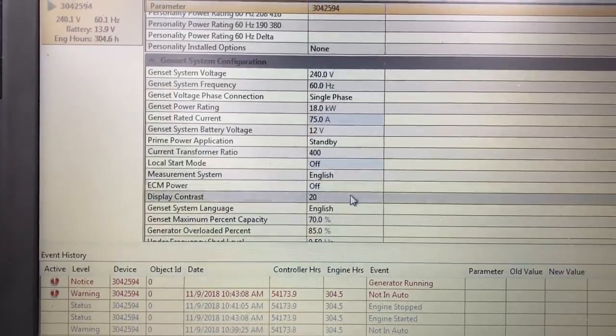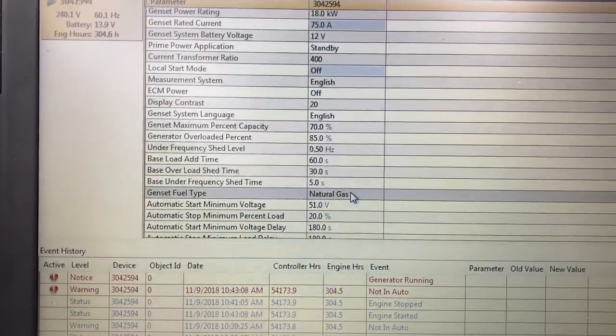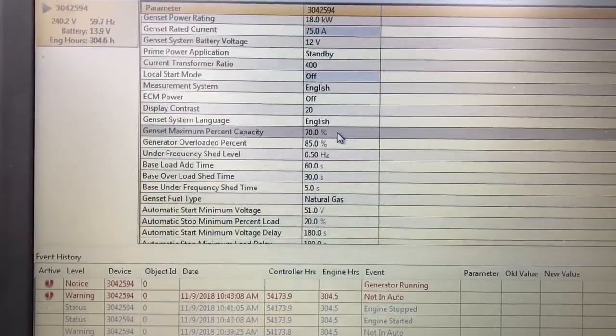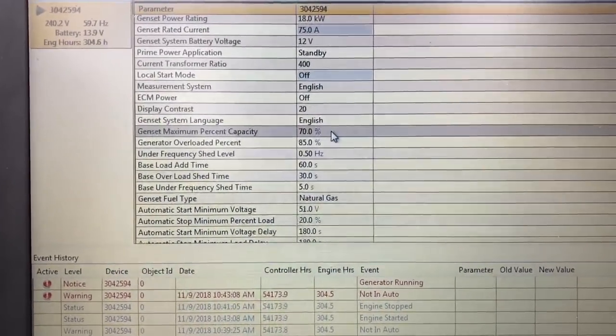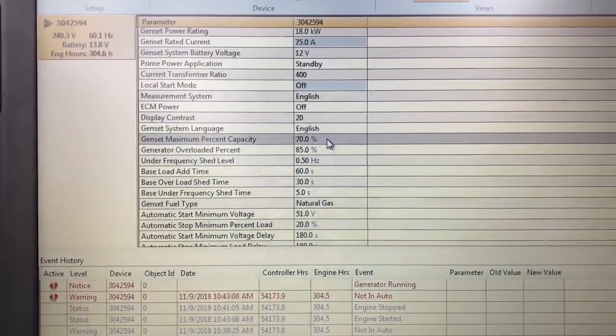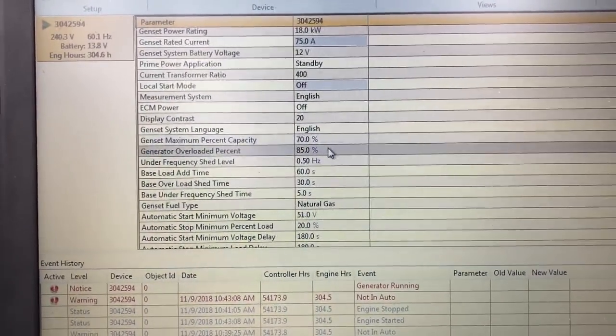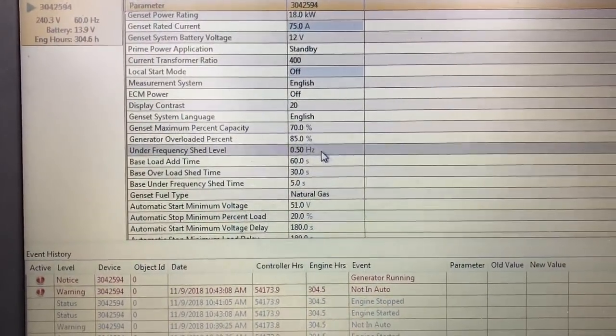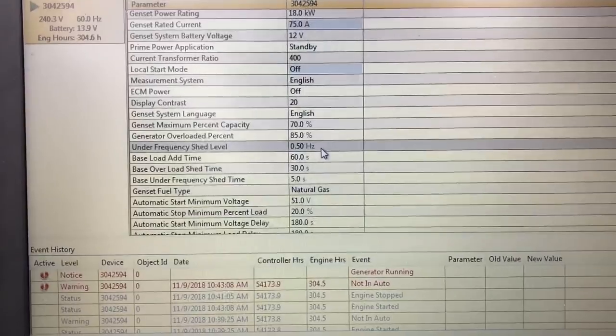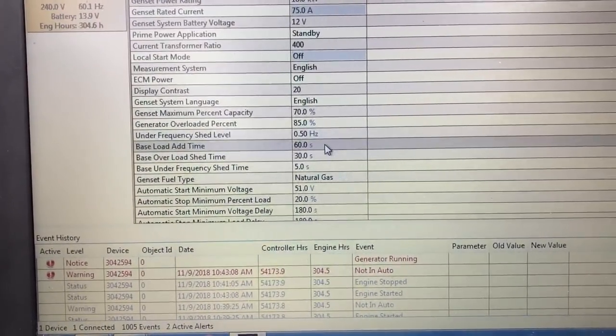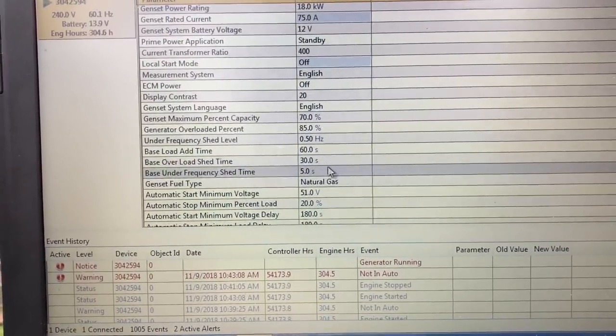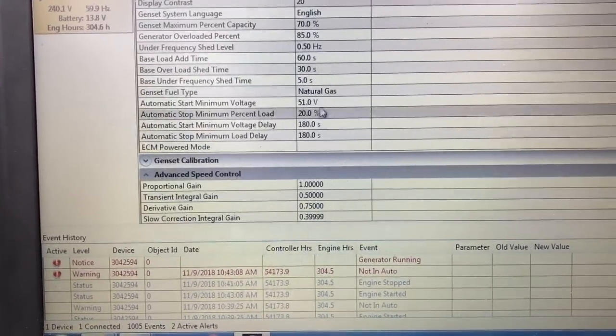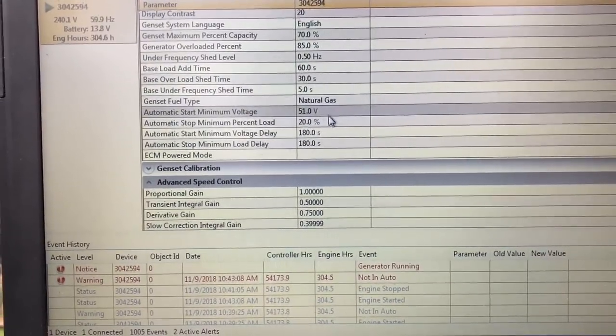The display contrast is at 20. Now, this is the interesting thing. The maximum percentage capacity is only set for 70% because you do not want to cook your motor. You don't want to be overloading. Your overload protection is at 85%. Your under-frequency shed level is at 50 hertz. If you go down to 50 hertz, you're going to shed if you have a low shed device.